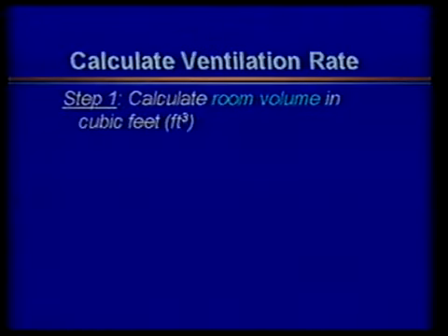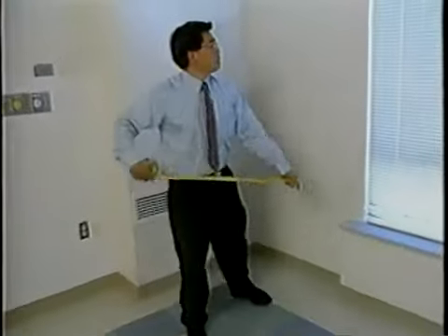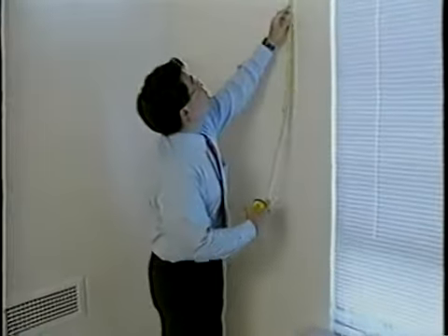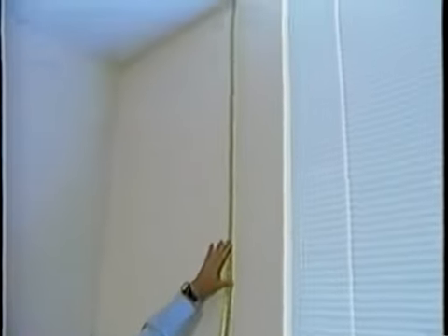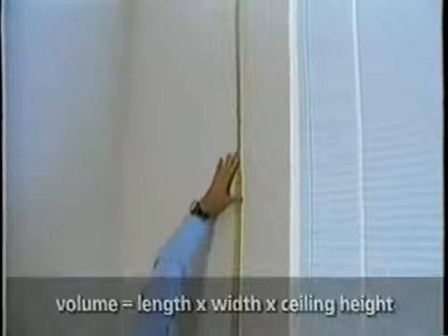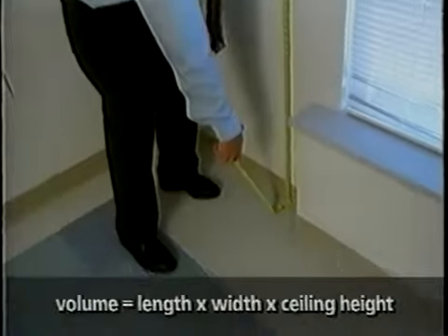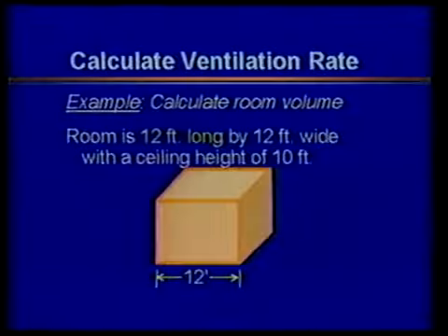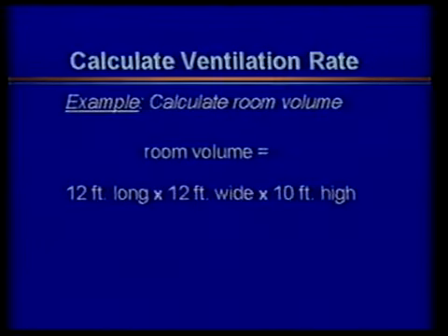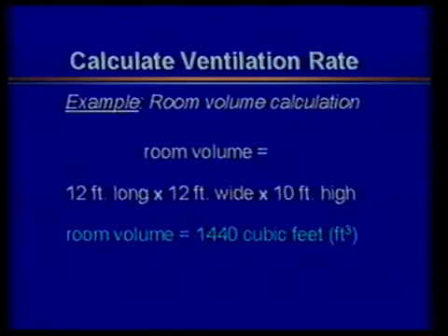The first step is to calculate the room volume in cubic feet. The tape measure is used to measure room dimensions. These dimensions are used to calculate the room volume. The volume is the length times the width times the ceiling height. We'll illustrate this with a simple example. Assume a square-shaped room 12 feet long and 12 feet wide with a 10-foot high ceiling. This would give you a room volume of 12 by 12 by 10, or 1440 cubic feet.